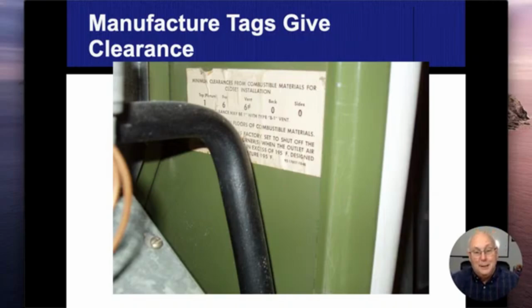Clearances around most furnaces are going to be pretty much 0 or 1 inch, so they could be put into a tight box. Natural draft furnaces or mid-efficiency furnaces with open burners in the front are typically going to be 6 inches, all right? And there's going to be a little chart on there where it talks about the left, the back, the front, the right, and so forth, and how many inches of separation. So on this one, for the very top of the furnace, they want you to have 1 inch. The front of it, because it's a natural draft furnace, they want 6 inches so we don't block the air coming in there. Where it says vent and it says number 6, that's because it's gas. They're really talking about 6 inches around the vent connector for combustible materials, and then we could actually be touching the back and the sides to combustible materials.